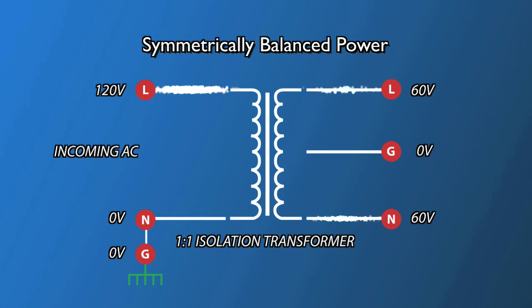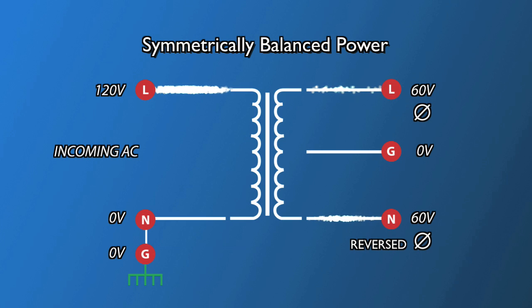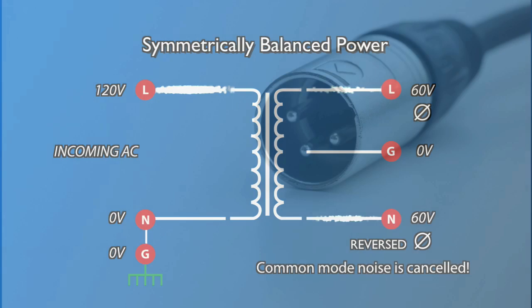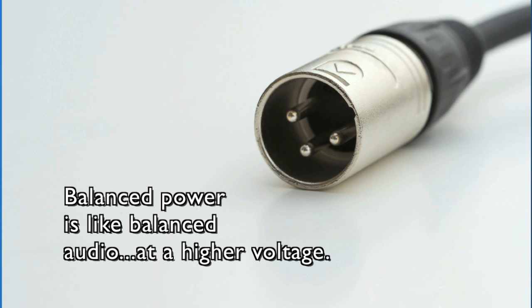What's significant about this is that the two 60 volt AC terminals are now in opposite polarity, so the symmetrical AC noise, or common mode fields, cancel. This noise reduction is extraordinarily efficient and linear across a huge frequency range, or bandwidth. The transformer has completely reworked your incoming AC, and the result is perfectly clean power devoid of common mode noise. Think of it this way: it's like balanced audio, but at a higher voltage.